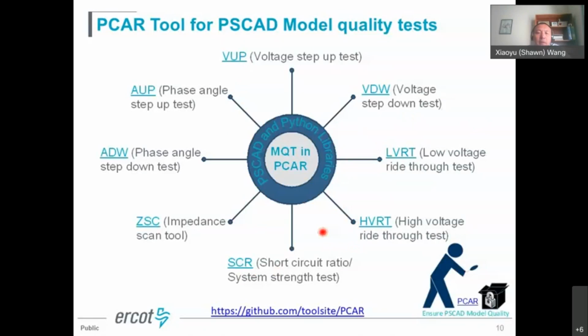Specifically for the PSCAD models, we also include phase angle step up and step down tests, and the impedance scanning tool, which can be used to scan the IBR PSCAD models to generate impedance profiles in both subsynchronous and supersynchronous frequency ranges.